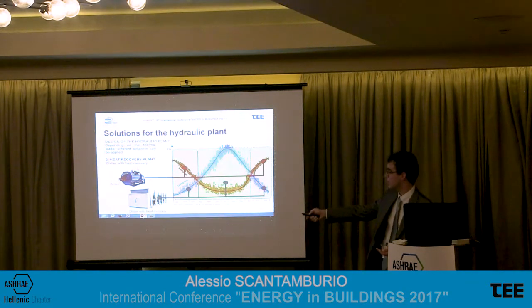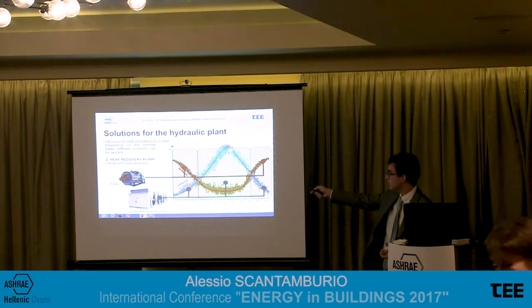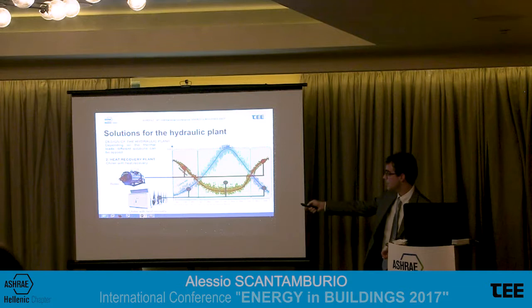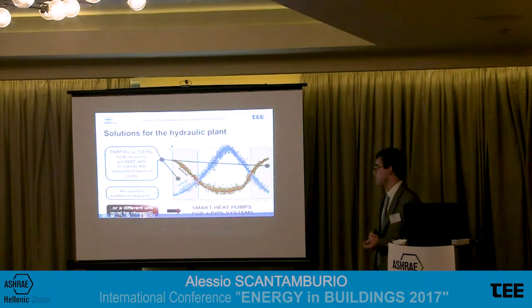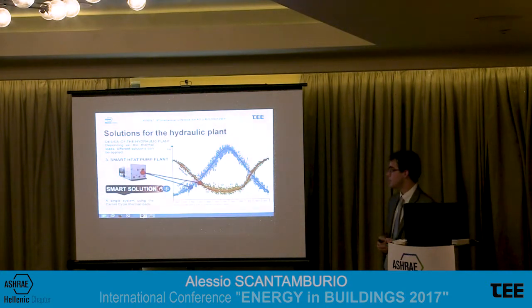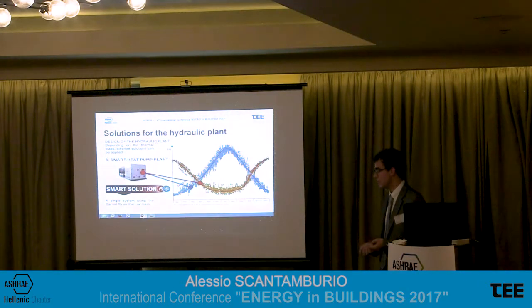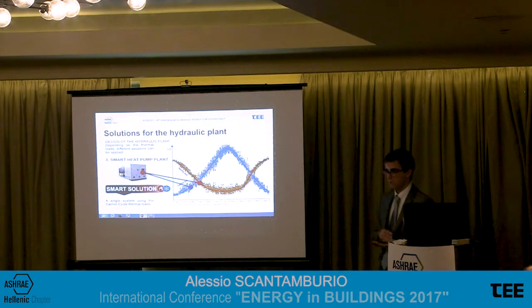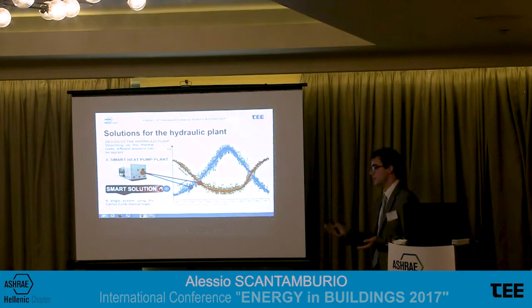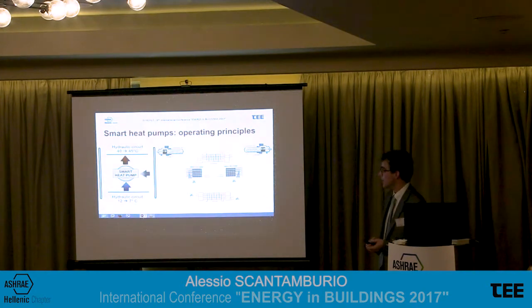Okay, so chiller with heat recovery works alone inside this area here, but still needs an auxiliary system to work here because it is not enough. And this is why there is room for four-pipe units. In fact, a four-pipe unit is really a smart solution that doesn't need any additional equipment, any additional gas boilers, without any problems in terms of combining different thermal loads, whether the cooling is higher than the heating or the heating is higher than the cooling. And now we will have a closer look at why it is possible from a technical point of view.